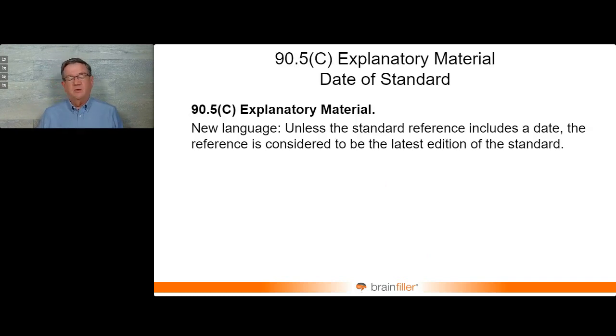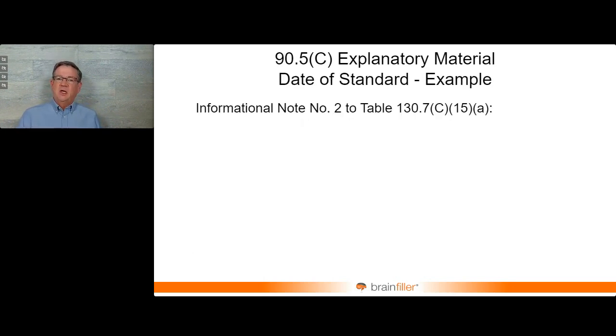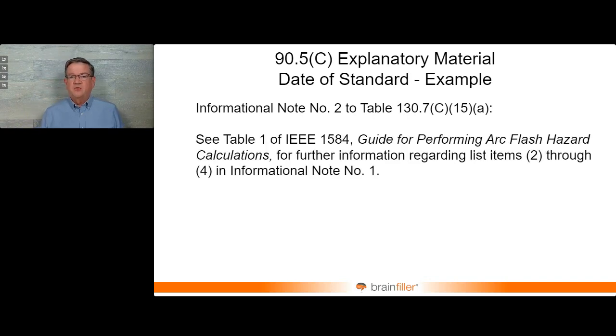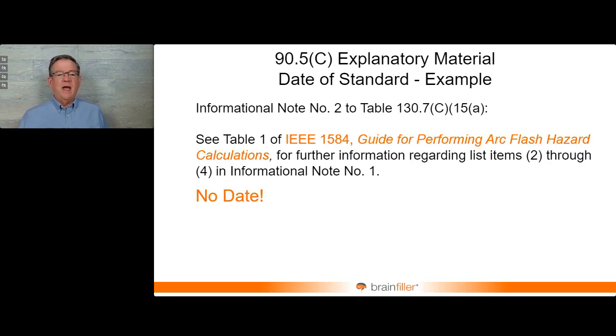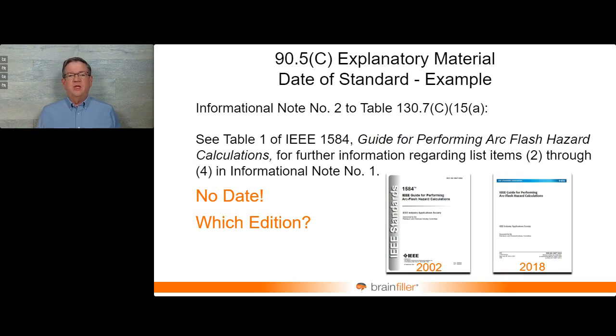The explanatory material, this was really long overdue. I think it was kind of understood by a lot of people, but if you don't put it in writing, how are you going to enforce it? And that was about if there are standards that are referenced within NFPA 70E, sometimes they will list the edition, sometimes they don't. And as an example, IEEE 1584 is referenced in NFPA 70E, but it didn't say which edition. I think most people would think, well, it'd be the latest one, wouldn't it? It should be, but that wasn't really clear. So now what we have is there's language that states that if the date is not provided, it's implied that it'll be the latest edition to be used.